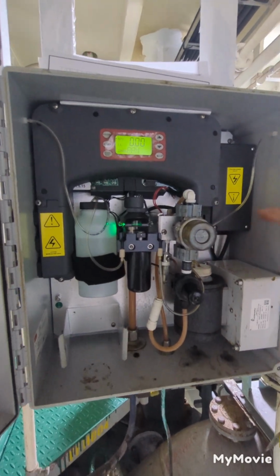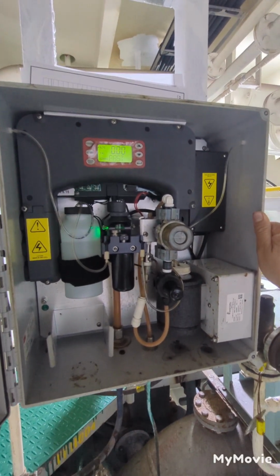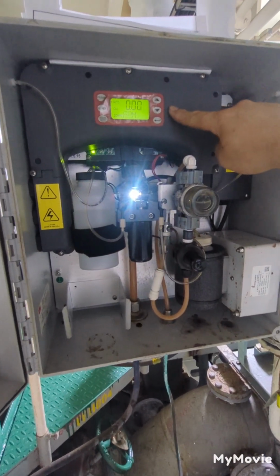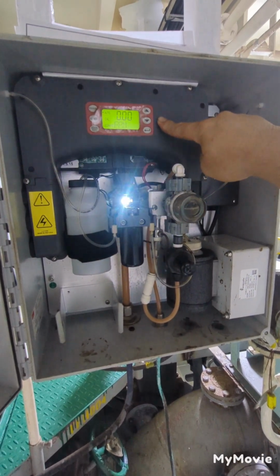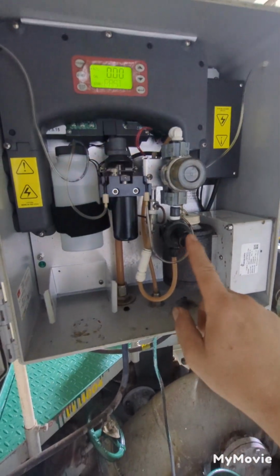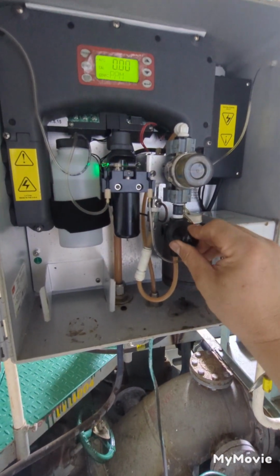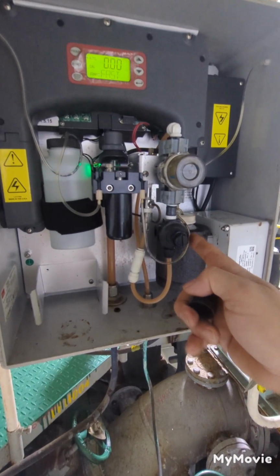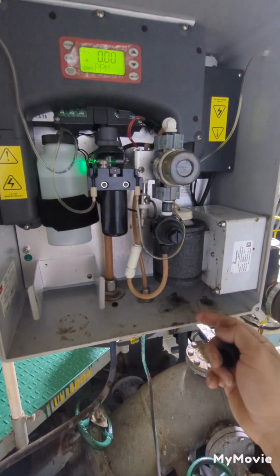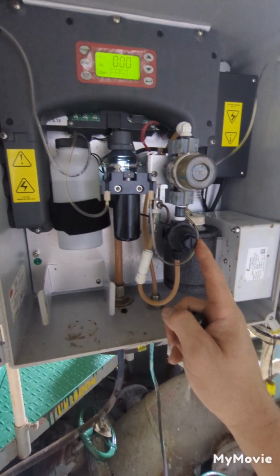So this is one of our CLX, or TRO sensor measuring instrument devices, and as you can see, if there is no water on it, there is a special regulation valve here. Once you rotate this valve in a clockwise direction, the water will flow with much volume. But when you rotate this valve the other way, you can have a small amount of water to penetrate inside the cuvette.